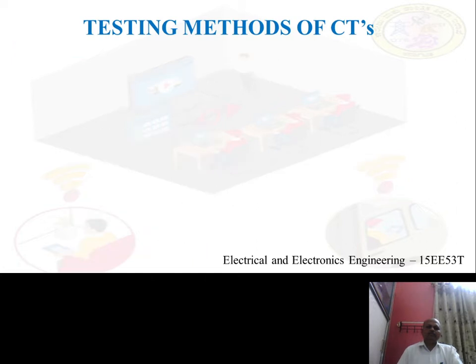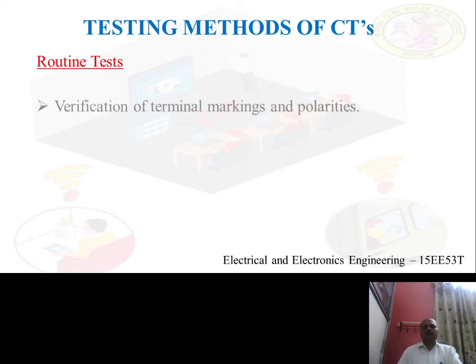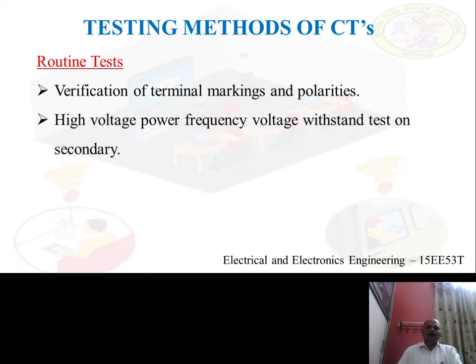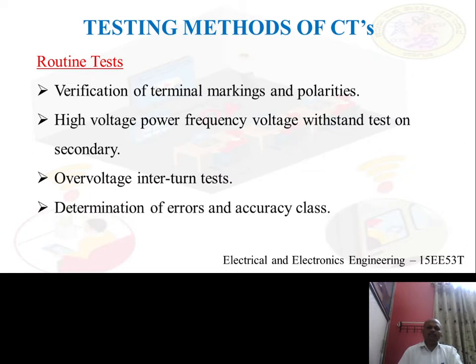The tests conducted on CTs during routine tests are: verification of terminal markings and polarities, high voltage power frequency voltage withstand test on secondary, over voltage interturn test, determination of errors and accuracy class.